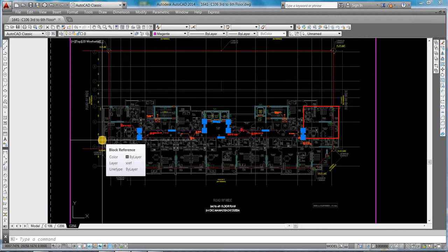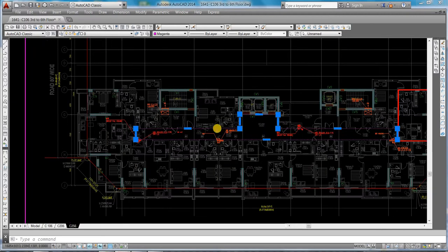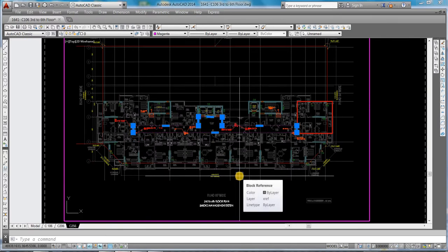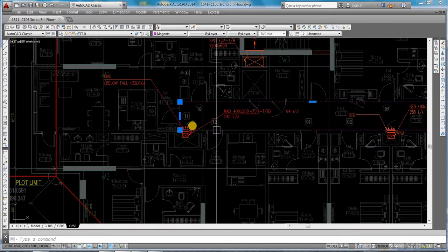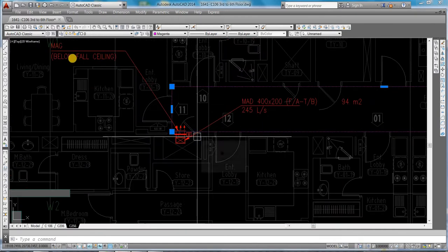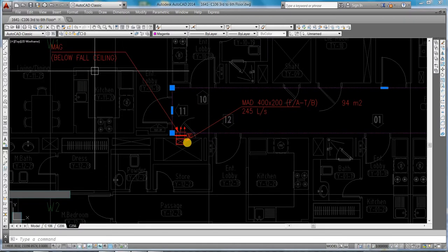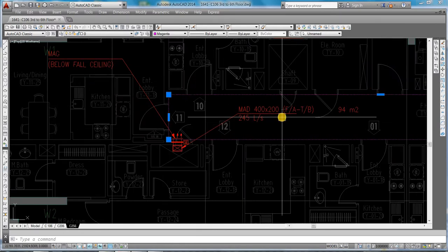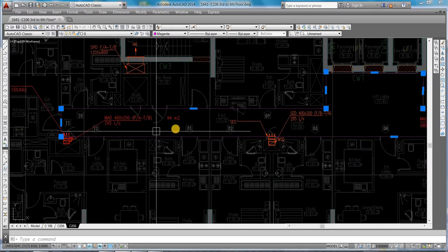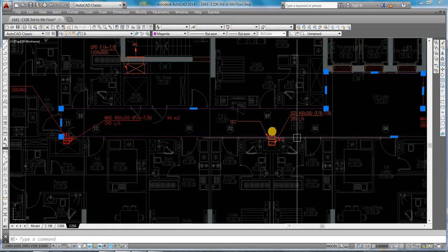Some countries don't want a smoke corridor system at all. Nowadays, all smart cities are providing smoke ventilation in high-rise buildings. In this smoke ventilation, normally we provide the makeup area below the ceiling, with a motorized damper and grill size, everything. The grill size is the same as the supply. The extract here also follows the same method, except at high level above the ceiling.